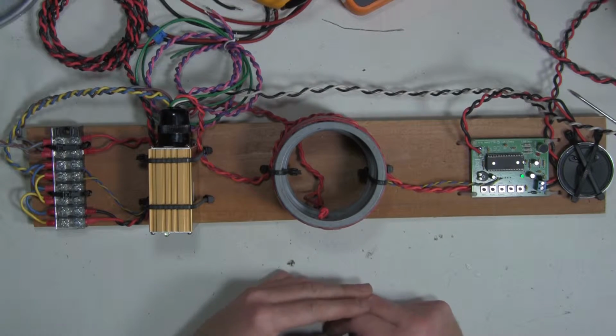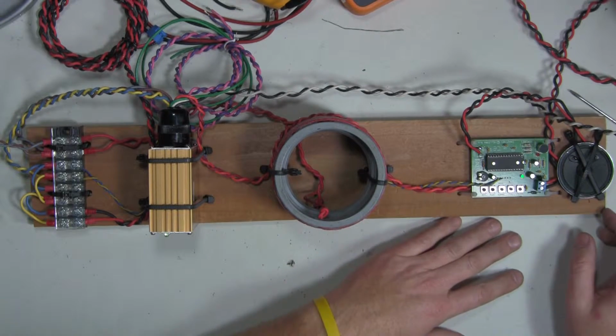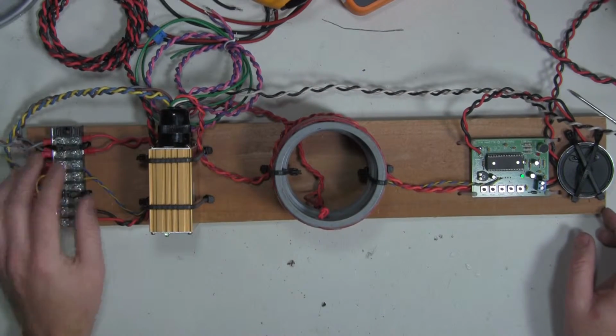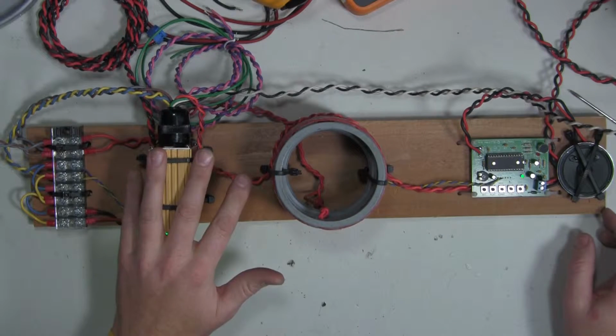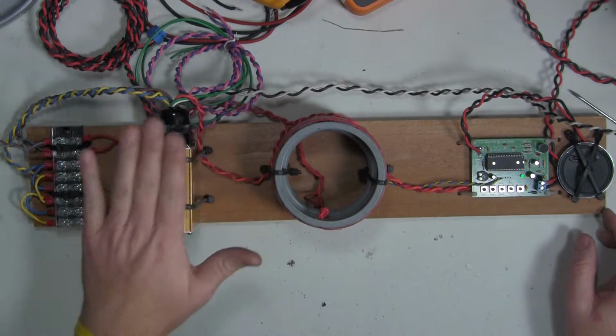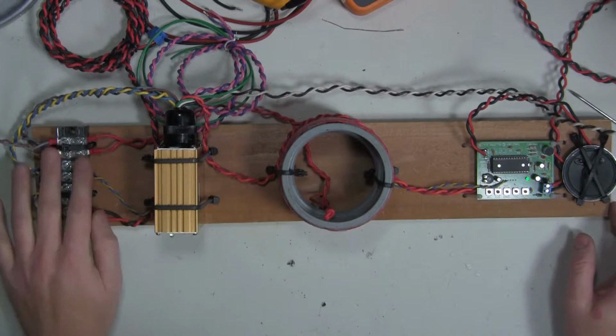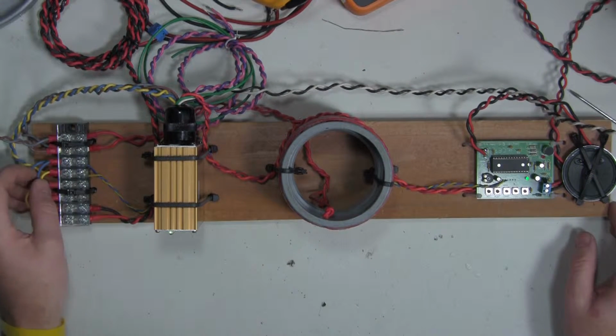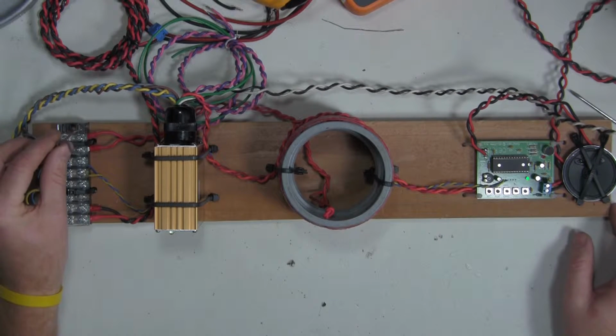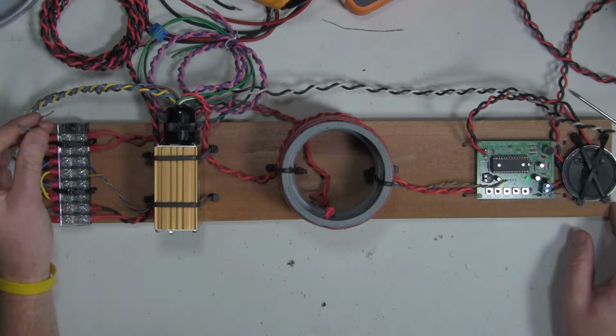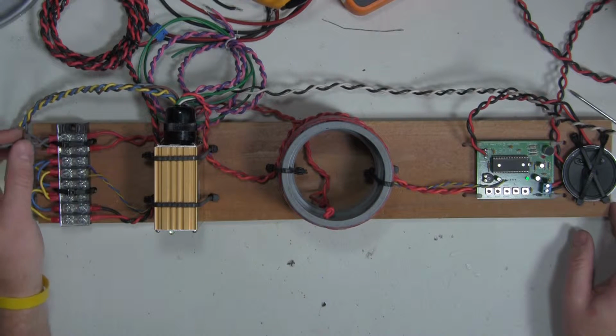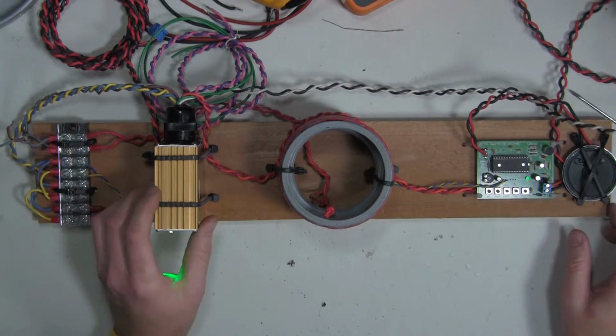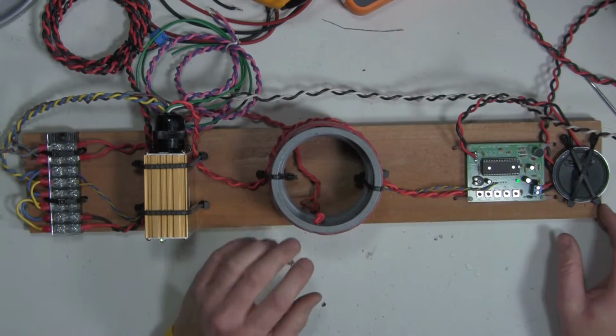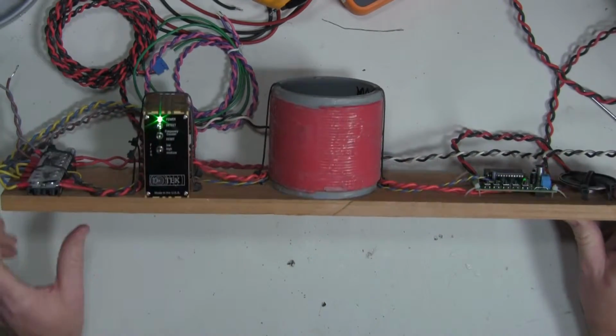Alright, so this is what the final display looks like. Everything from here on over is the interactive display part. The coil and loop detector and this harness to a certain extent are all the permanent things that you would need in order to test a loop detector with a known good load. The terminal strip may not be necessary. You don't necessarily need to jumper everything together, but it would be nice to have the ability to actually connect multiple probes directly to the output of the loop detector, so you can measure different things: frequency, current, voltage, and possibly duty cycle.